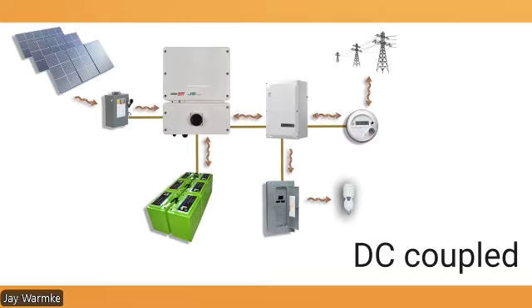And you can put in voltages up to 600 volts in a residential battery bank, as long as the battery system itself is considered inaccessible, that it can only be serviced and accessed by a trained technician. An example might be a Tesla Powerwall, a self-contained unit that can only be worked on by certain Tesla-certified folks. Those can go all the way to 600 volts. So we're starting to move towards higher voltage battery backup storage.